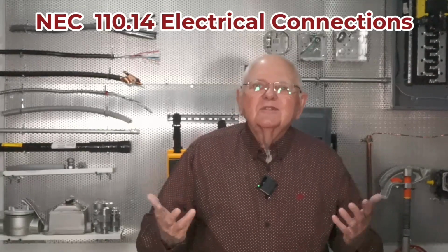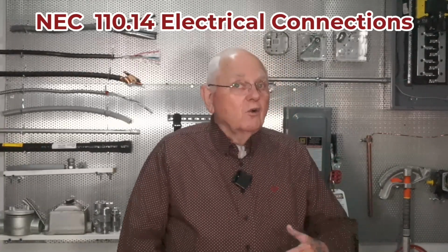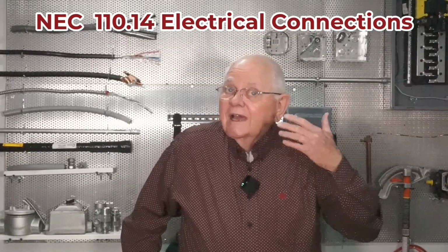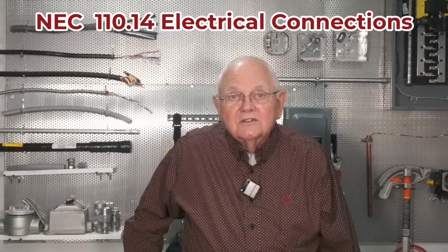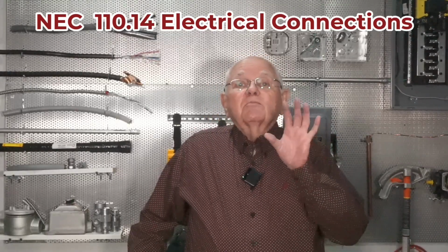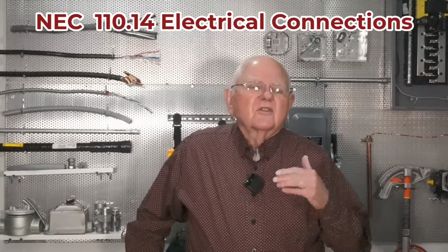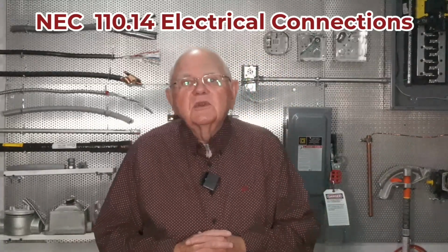Not only does it damage the connection mechanically, but once again, it could now provide too much resistance for that effective ground fault current path. Then I've got a problem. If my overcurrent protective device up here doesn't operate when it's supposed to, I've got a fire. Maybe somebody's going to get electrocuted or shocked. Not a good situation, huh? I'm not meeting the purpose of my code, to protect people and property from the hazards arising from the use of electricity, the practical safeguarding of all that. So anyway, pay attention to corrosion between dissimilar metals.